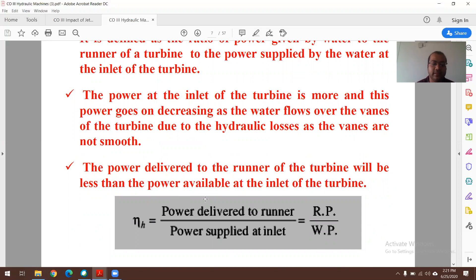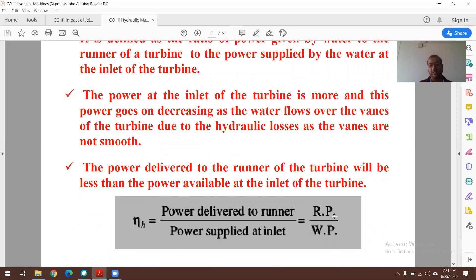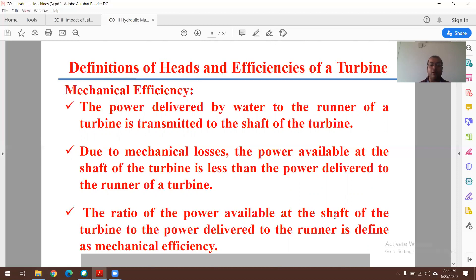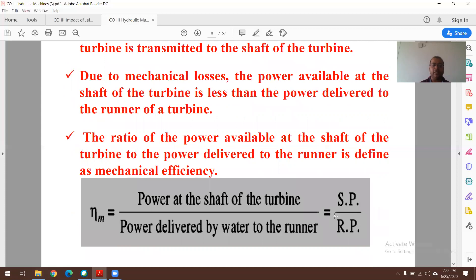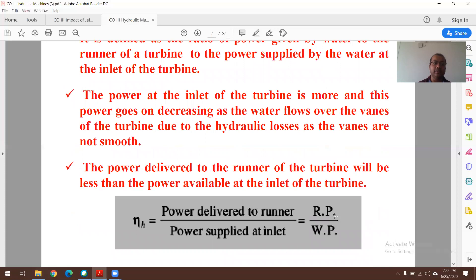Mathematically, hydraulic efficiency ηh = Runner Power (RP) / Water Power (WP), multiplied by 100 for percentage. Mechanical efficiency is the ratio of power available at the shaft of the turbine to the power delivered to the runner. Due to various mechanical losses, power at the shaft is generally less than power delivered to the runner. Mechanical efficiency ηm = Shaft Power (SP) / Runner Power (RP).